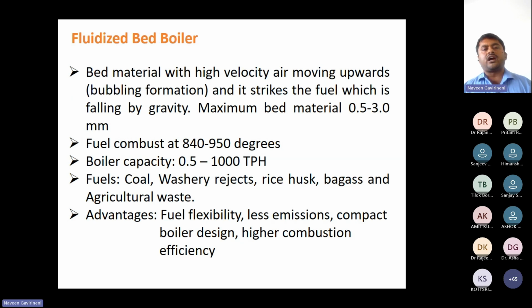I already explained there are different technologies of the boiler: AFBC, CFBC, atmospheric fluidized bed combustion, and pulverized fuel. These boilers are used nowadays. AFBC is for small capacity, fluidized bed combustion for medium to somewhat high capacity, and PF, pulverized fuel, for high capacity only. That means 660 and 800 megawatt. All NTPC units of more than 600 megawatt come under PF, but less than 600 megawatt come under the fluidized bed boiler. For lower capacity they also use PF, but it will not give that much efficiency.